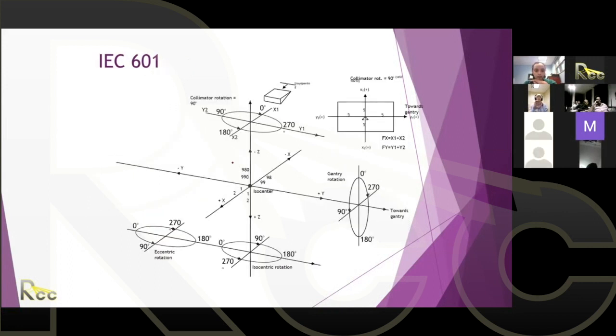But the most important thing is the LINAC rotation. If I'm using 601, the wedge would be in the X1, X2 direction. If this was an Elekta using 601, then the wedge would also be in the X1, X2 direction. But if it was 1217, then the wedge would be in the Y direction.